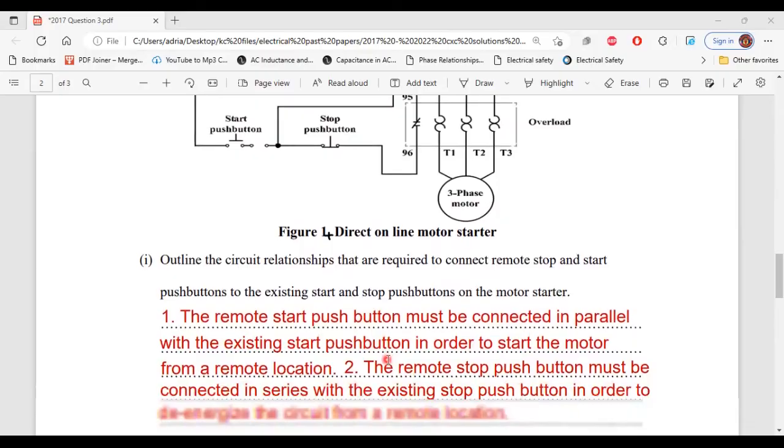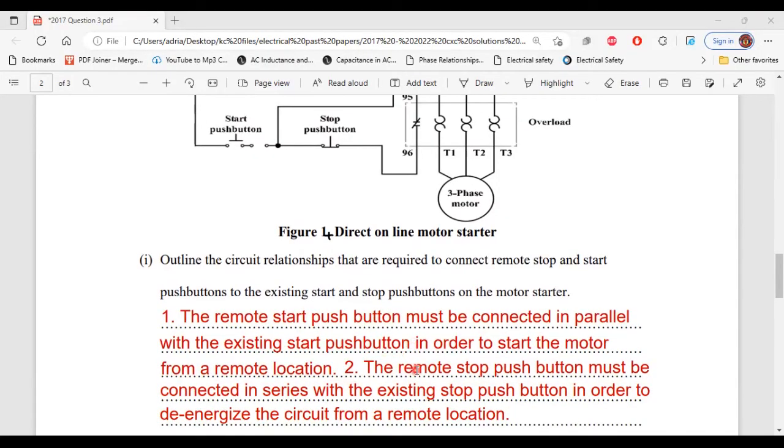For the remote start push button, you must connect it in parallel with the existing start push button to start the motor from a remote location. For the stop push button, it must be connected in series with the existing stop push button to de-energize the circuit from a remote location. That's what they're looking for. That's it for part one of C.